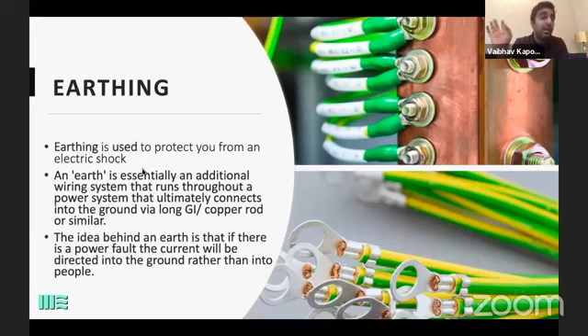Now, most of the problems are that you are not getting proper earthing. There is an earth fault which is happening. Why is all this happening? Firstly, the earth needs to be done properly. Every venue, every location, the soil is different. You need moisture in the soil to get proper values of earth. In a garden where the soil is always nourished, it is always watered, so ultimately it has moisture in the soil. If you go to a rocky area, just as an example like an MMRDA ground where it is rocky, we need to nourish the soil each and every time.